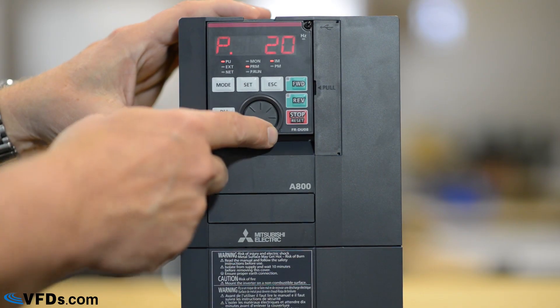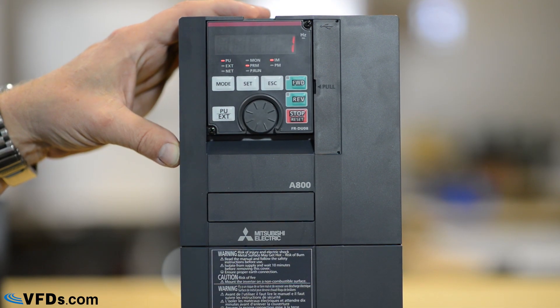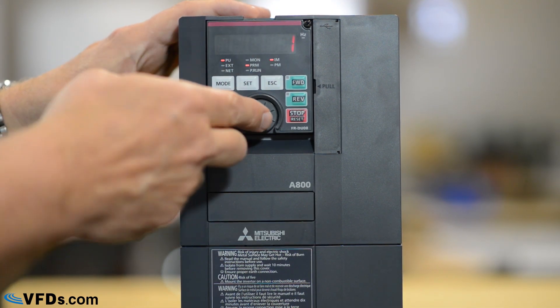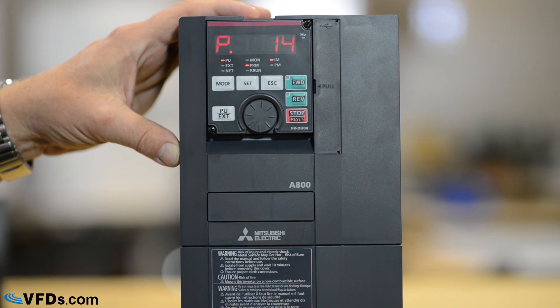Finally, we want to go to parameter 14. Parameter 14 tells us whether it's a constant or variable torque drive. In this case it's set for variable torque mode. I'm going to change that to zero, which puts it in constant torque mode, and set that.